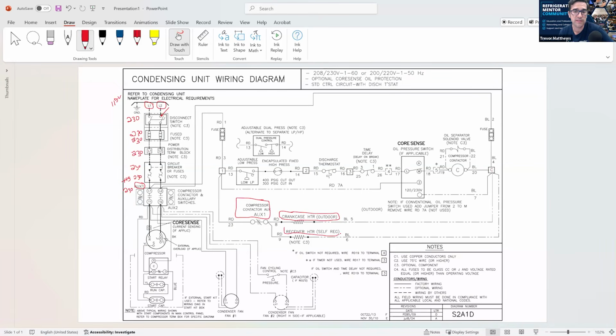So on this system, self-regulated, it says receiver heater, which means I'm assuming there's a thermostat on there. Well, it will, and I'll have to double check that in the manual. So that compressor is off. We have the crankcase heater running on that compressor because we always want that to be running so that we don't get any migration into the oil of that compressor. So the compressor contactor is open at this point.